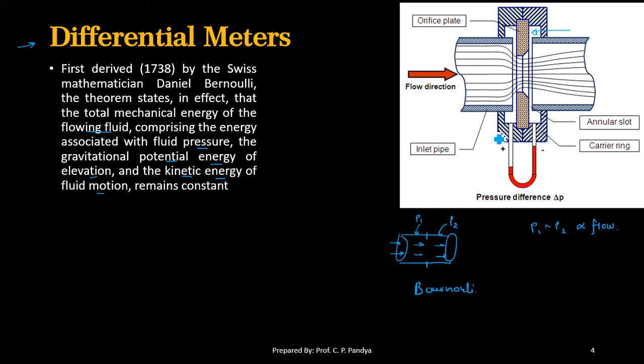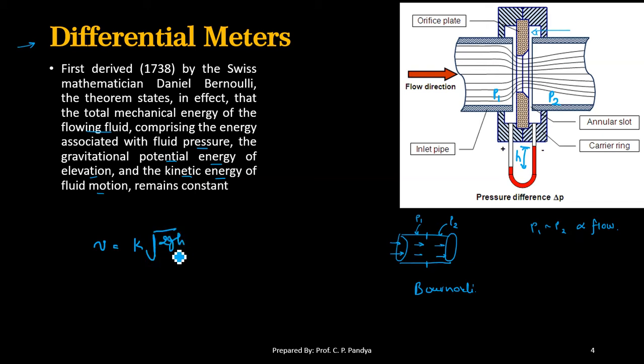Here we get the difference in heights, indicated by H. If we take the pressure as P1 at one point and P2 at another, then the velocity equation becomes: V = K × √(2gh/ρ), where g is the acceleration due to gravity, h is the differential height or differential head, and ρ is the density of the flowing liquid.